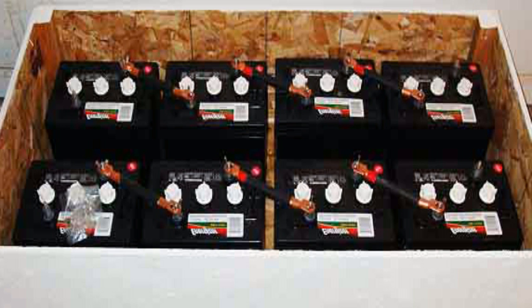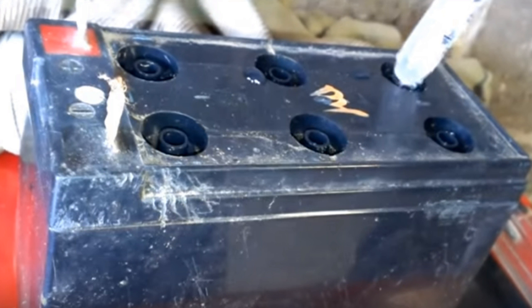Number 2: Proactively Prevent Corrosion. Even if you use the most expensive, high quality batteries in your battery bank, it won't be of much use if corrosion or acid is on them. Before you assemble all of the components of your battery bank, make sure to individually coat the terminals, wire lugs, nuts and bolts with a non-hardening sealant. You can also apply a thin coating of petroleum jelly to the battery terminals for extra protection. Lastly, seal exposed wire at a terminal lug using submersible rubber splice tape or something similar. This must be done before assembly to ensure all parts are equally protected — if you apply protective substances after assembly, dirt can get into small spaces that weren't properly coated.